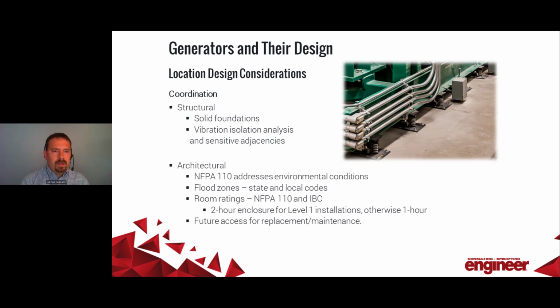So, as we're going through the design process, we want to make sure that we're taking into consideration location. Where are we putting this generator? In the case of structural, which I personally think is probably of paramount importance, if we're installing it on grade, if we're installing it on the 7th floor of a high rise, if it's on the roof on the 22nd story penthouse of a high rise building, it's important that one, we have solid foundations, but two, that we're designing for consideration of vibration and sound transference into adjacencies. Maybe this is a research building where you've got a vivarium floor above or below or nearby. We want to make sure that we're minimizing propagation of vibration and sound into those more sensitive adjacencies. So an analysis is probably warranted in that case, in conjunction with our structural discipline.